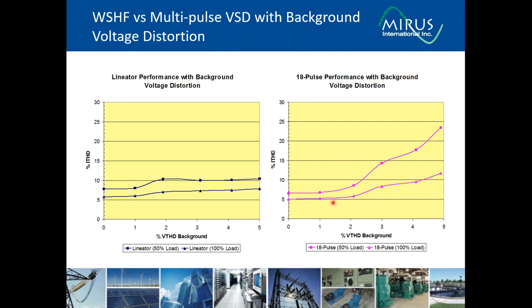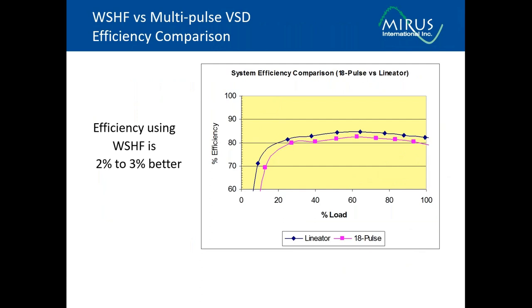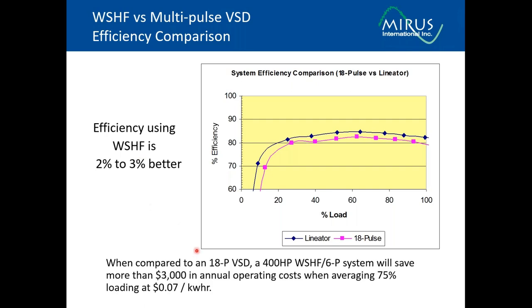With the 18 pulse system, the performance dropped off dramatically as we approached higher voltage distortion levels, and certainly at lighter loading levels, the performance was rather poor. And from an efficiency perspective, we took measurements with the 18 pulse and with the 6 pulse in the filter, and the difference was about 2 to 3 percentage points across the full load profile. If you do a quick calculation, you can determine significant savings associated with that reduction in losses.